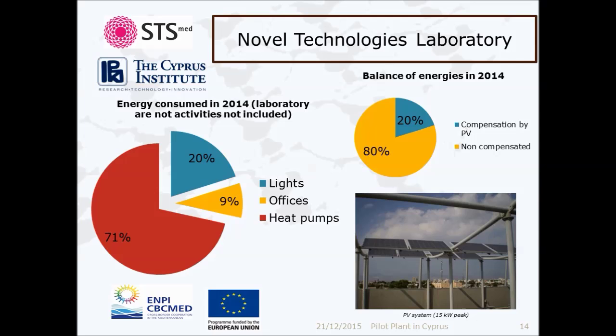So, by reducing the use of the heat pump and the chillers for the air conditioning, we reduce indirectly their electric consumption. The objective of the installation of the Fresnel collector is to reverse the proportions of 20-80% between compensated and non-compensated energies, and to have a new proportion of 80-20. So basically, to almost cover all the needs of the building.